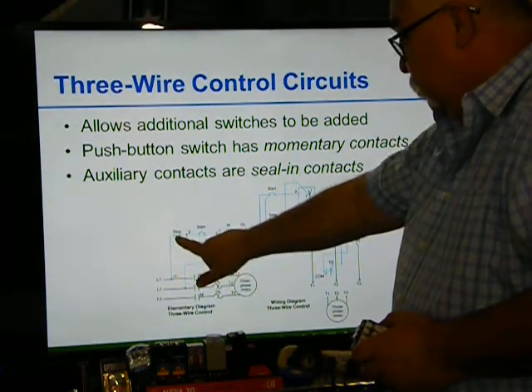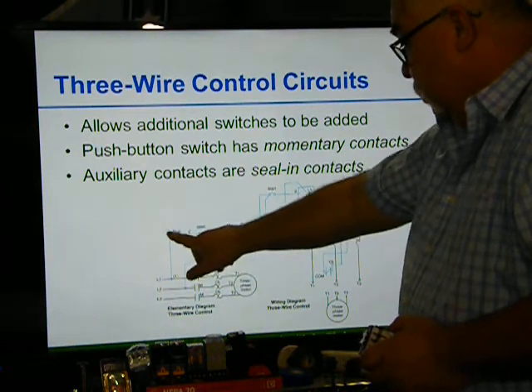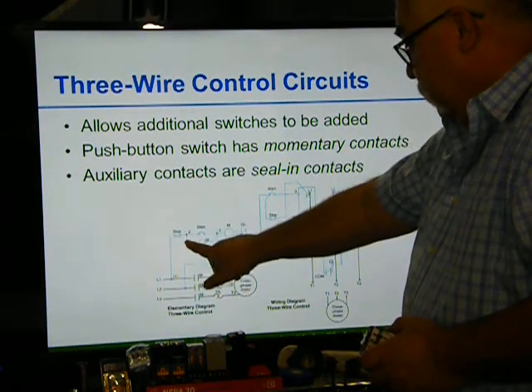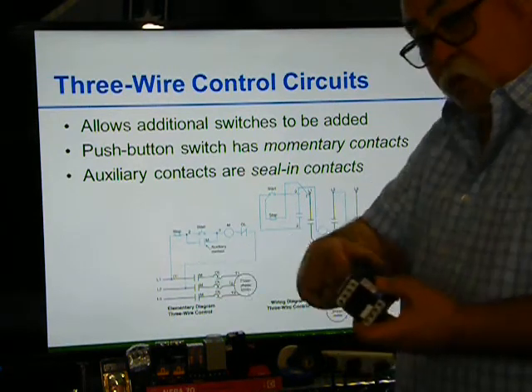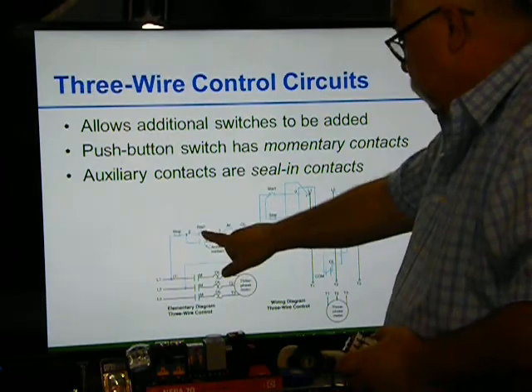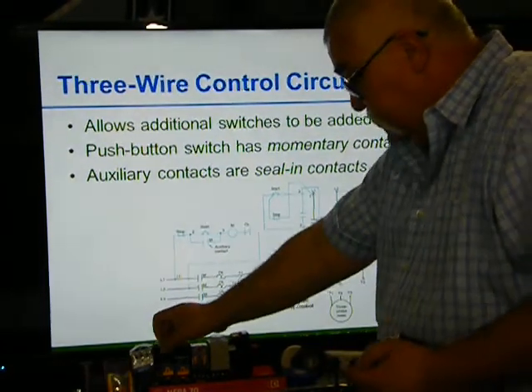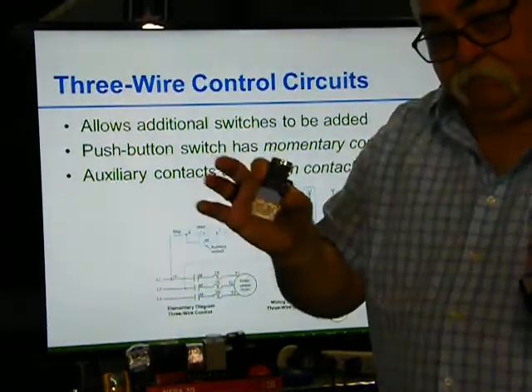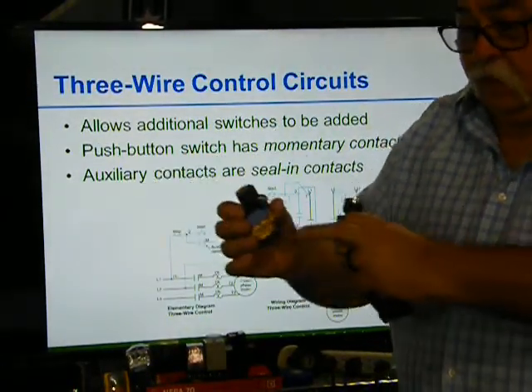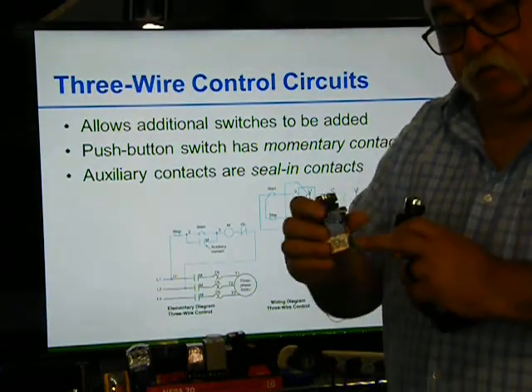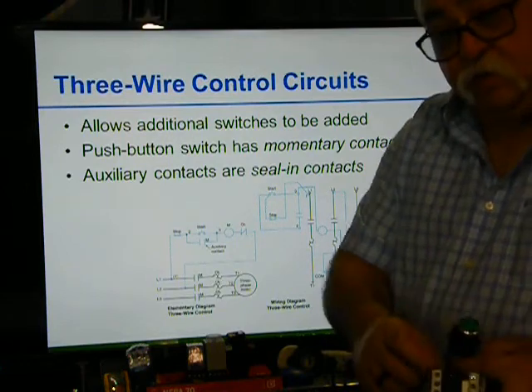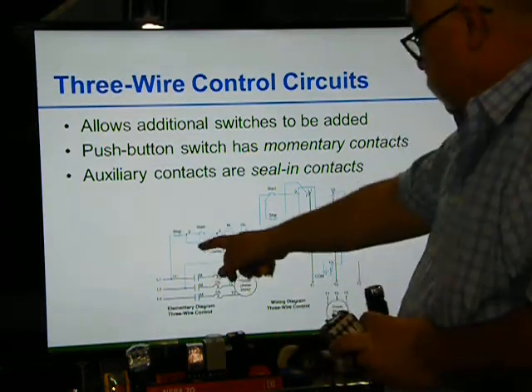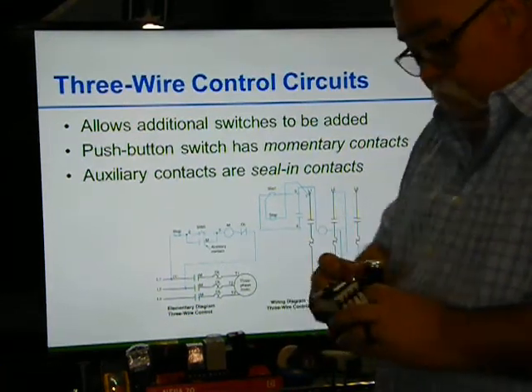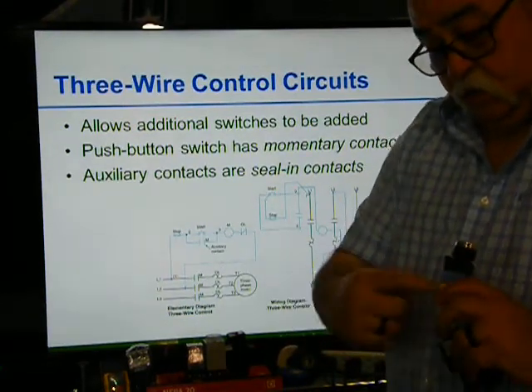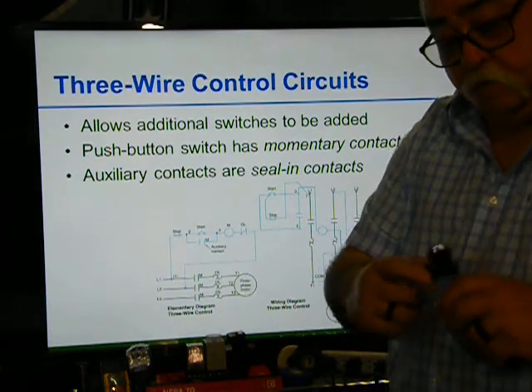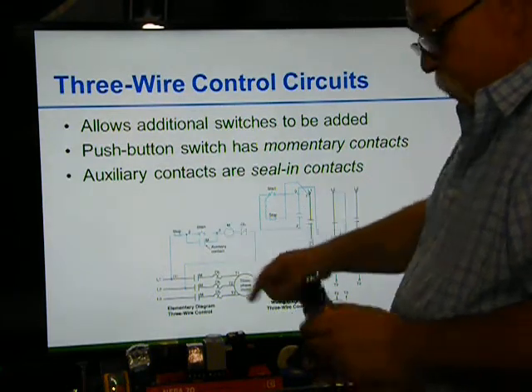Once I hit the start button, because you can see right here, I got 1 coming in, 2 going out, and here's my connection on the 2. I'm coming to the auxiliary contact, which is in here. That's at 3 and the 4. And then it comes off the start side on the switch. So I'm going to come in on the 1, come off the 2 to go to my switch. Off the 2 here, I would come across to the number 3 up here. And then that comes down to the auxiliary. And then it also comes to the number 3 on the green switch on the start. And then off the 4, I come across and it goes to the coil.